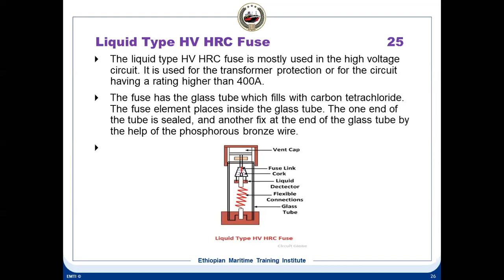So for high voltage, you have cylindrical type cartridge fuses. We have liquid fuses, but these liquid fuses we are not using on board ship. We have all cartridge fuses. Cylindrical type cartridge fuses we are using on board ship. The liquid type may be used in some substations and all. It's HV, HRV, HRC fuse. Okay, so these are the fuses, and then we'll go to some other slides.